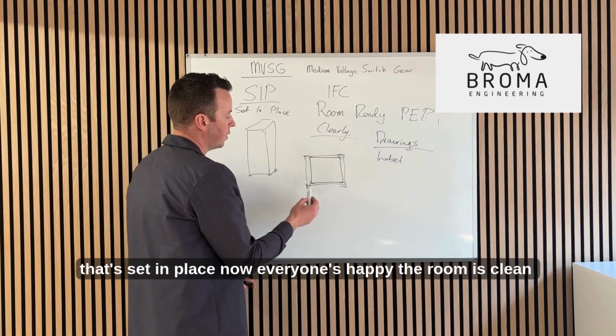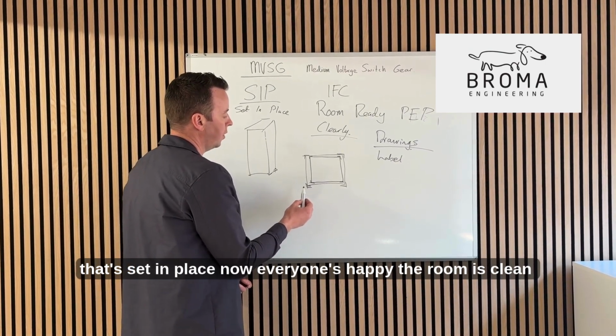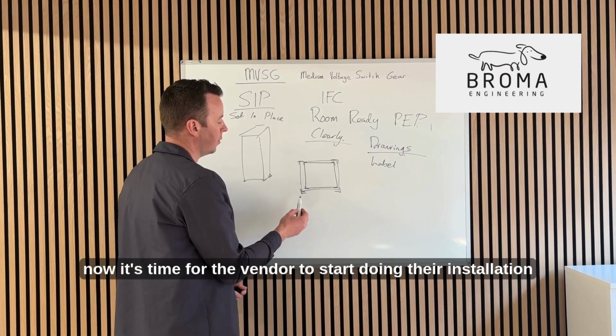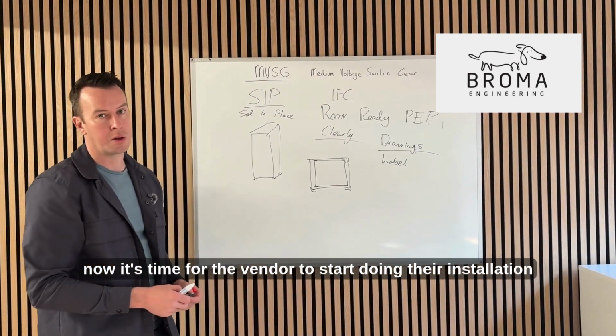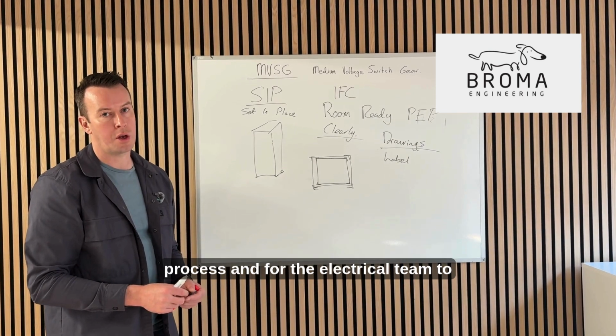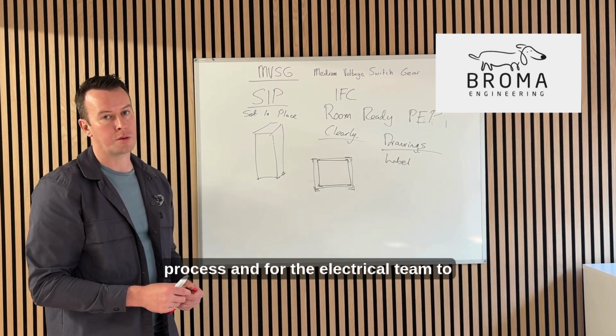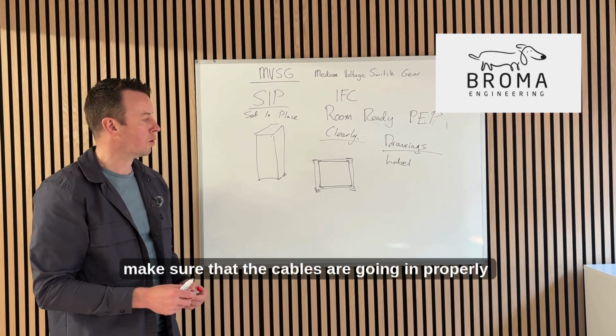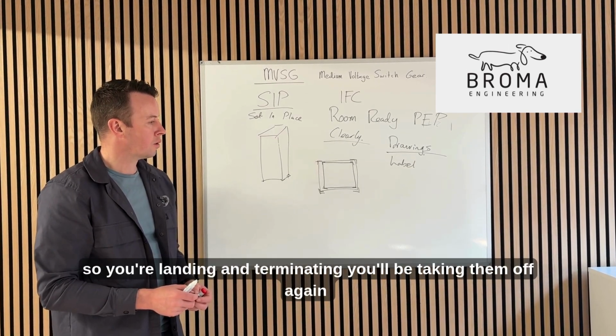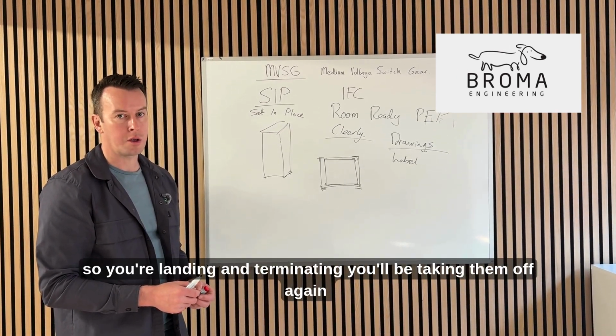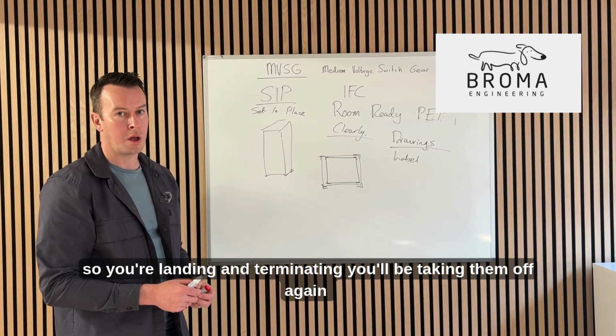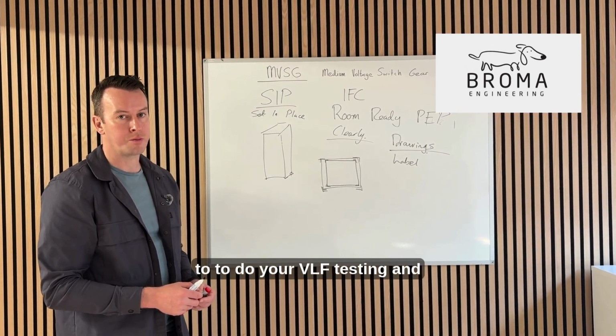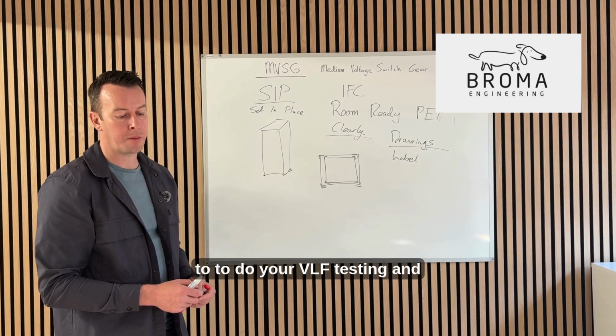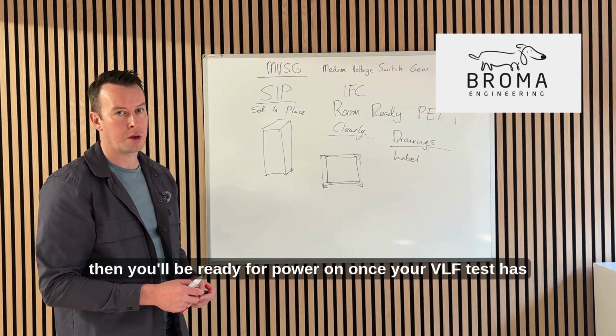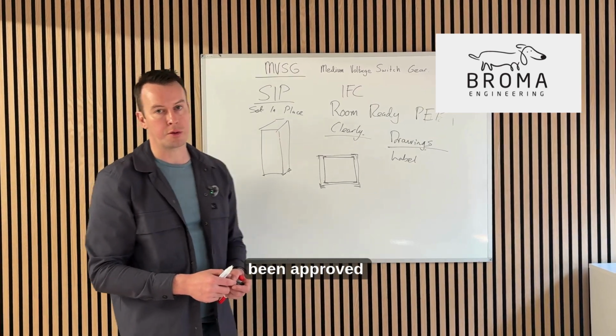Okay, that's set in place now. Everyone's happy. The room is clean. Now it's time for the vendor to start doing their installation process and for the electrical team to make sure that the cables are going in properly. So you're landing and terminating. You'll be taking them off again to do your VLF testing, and then you'll be ready for power on once your VLF test has been approved.